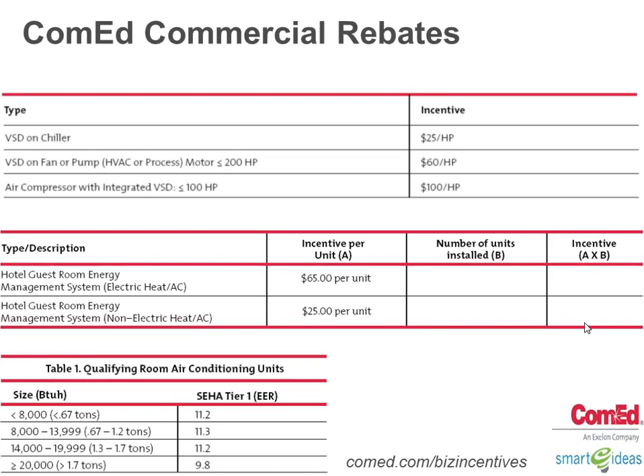You can put a variable frequency drive on a fan or a pump and get a $60 per horsepower rebate, which almost pays for the cost of a drive in many of these scenarios. Obviously, you still have to pay to get it installed, but it is a really good rebate. It's a very attractive dollar amount. If you put a VFD on a chiller, the dollar amount is actually lower, $25 per horsepower, because the payback is longer in those scenarios, but it's pretty fast on a pump or a fan. Typical paybacks are under 18 months when I do a VFD project, so it is a pretty good deal.